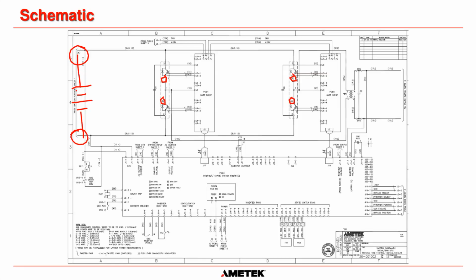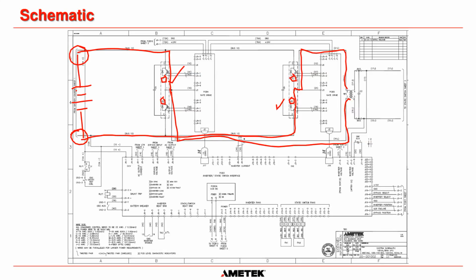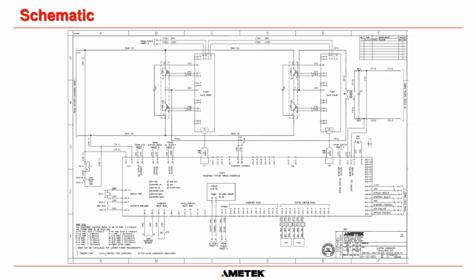Let's switch on Q1 and Q4. Power flows down through Q1 down to this point here. That goes down out to the transformer. Okay, and then the bottom side of the transformer gets connected to the negative through this IGBT back here, and that will give us our negative going pulse, because we've got this side is more positive than this side, and the same for the other side of things.